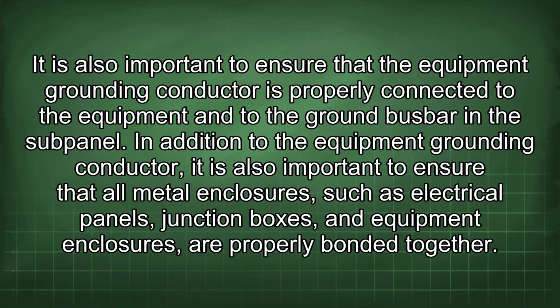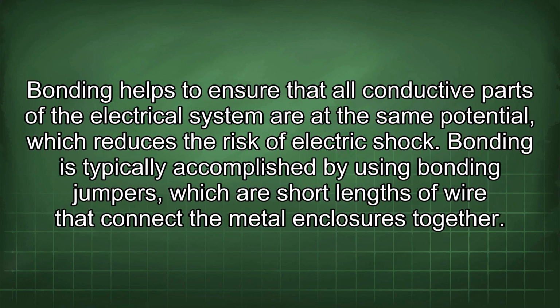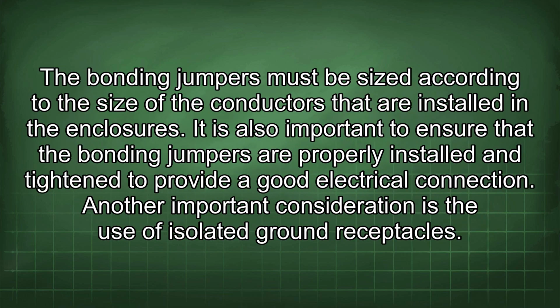In addition to the equipment grounding conductor, it is also important to ensure that all metal enclosures, such as electrical panels, junction boxes, and equipment enclosures, are properly bonded together. Bonding helps to ensure that all conductive parts of the electrical system are at the same potential, which reduces the risk of electric shock. Bonding is typically accomplished by using bonding jumpers, which are short lengths of wire that connect the metal enclosures together. The bonding jumpers must be sized according to the size of the conductors that are installed in the enclosures. It is also important to ensure that the bonding jumpers are properly installed and tightened to provide a good electrical connection.